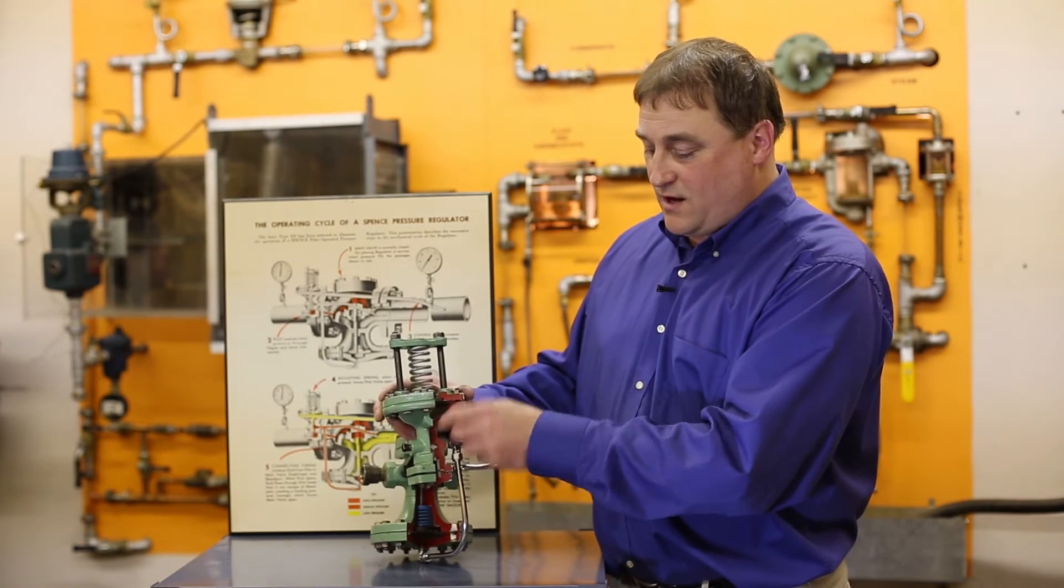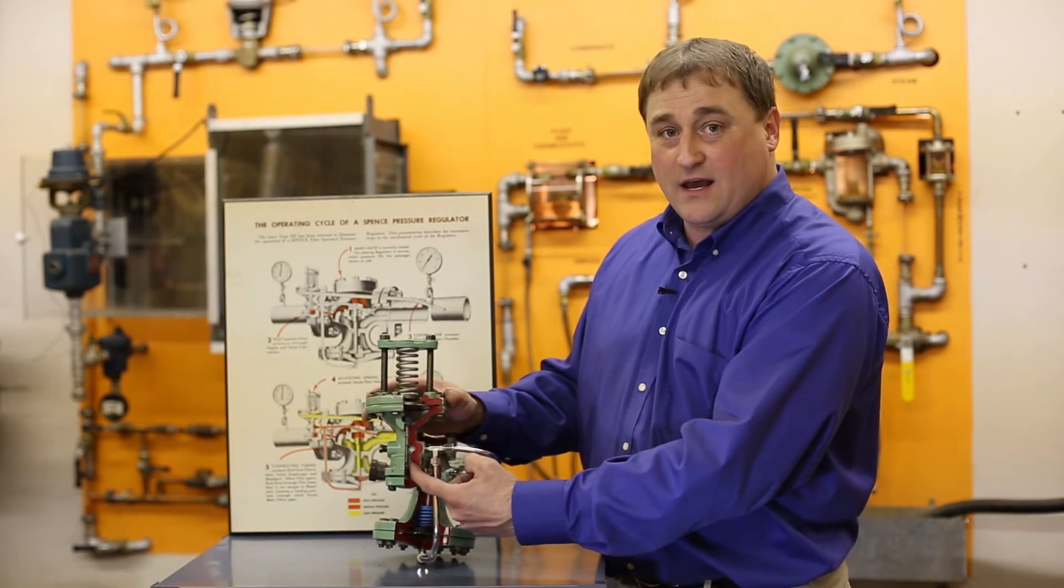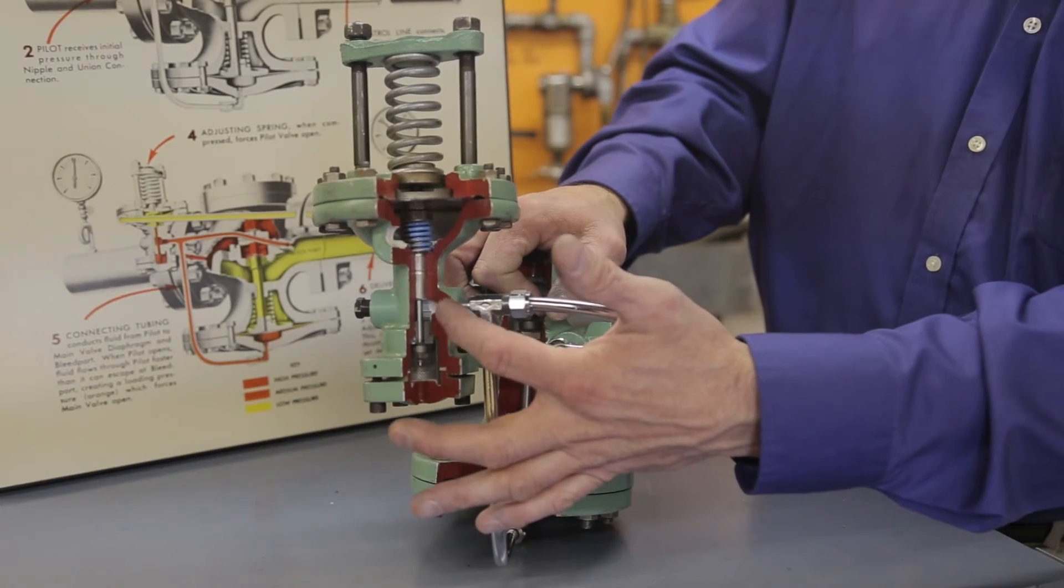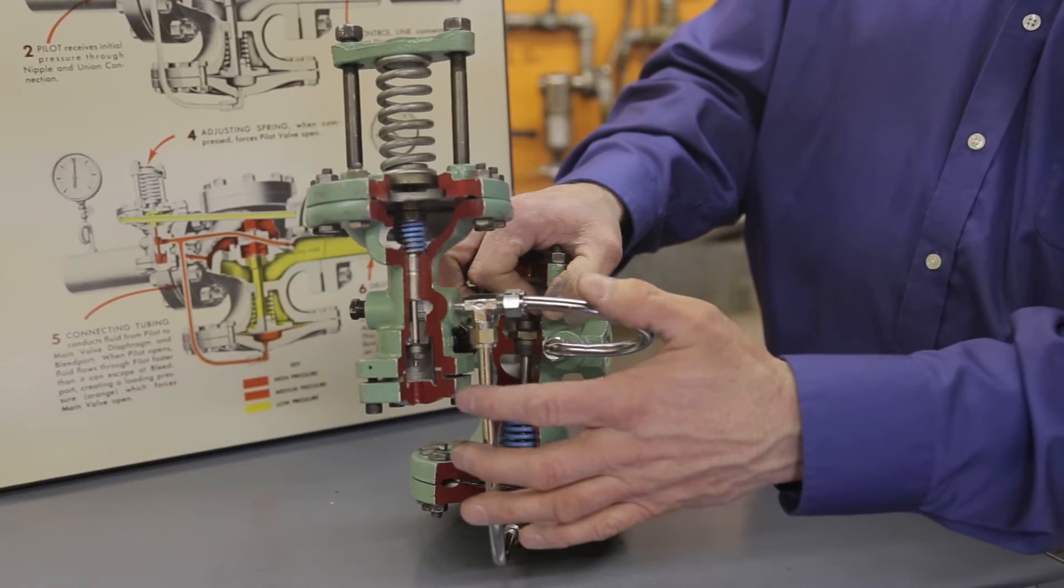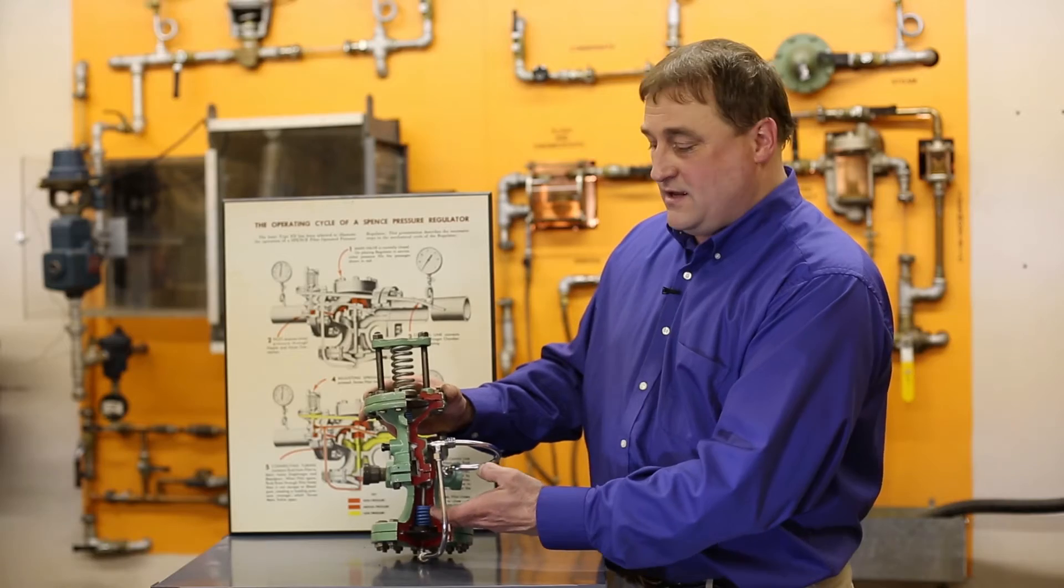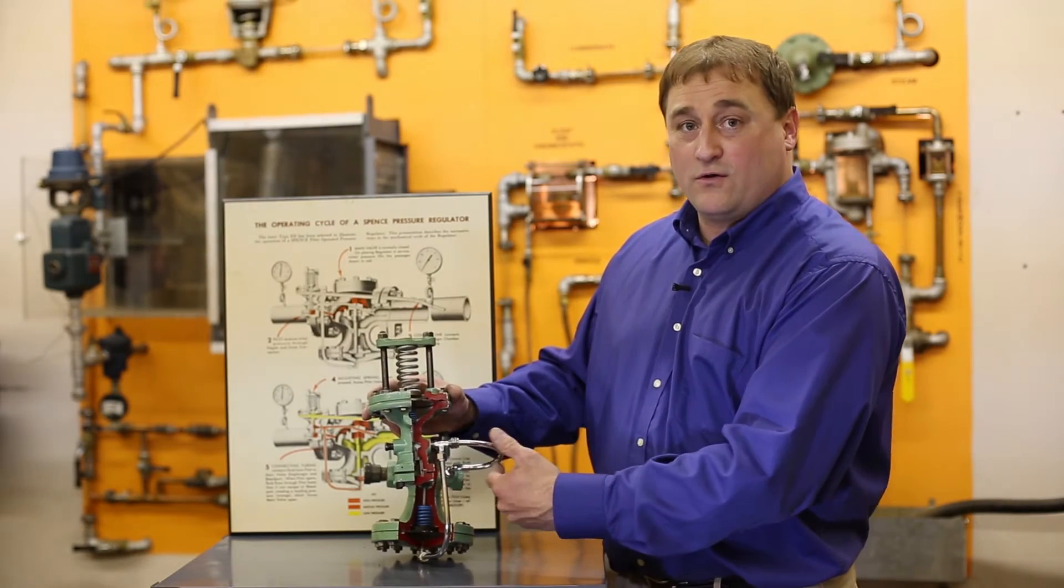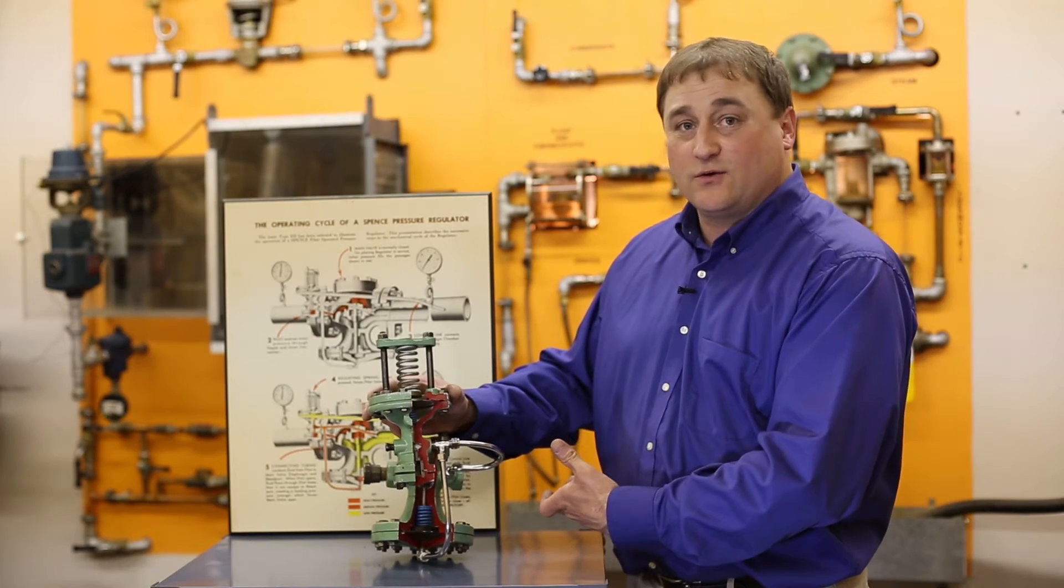It would overcome this pressure, push down on the smaller pilot-operated valve, which then increases the pressure in the tubing, and then would stroke this valve and try to get more flow through the valve to increase that delivery pressure.